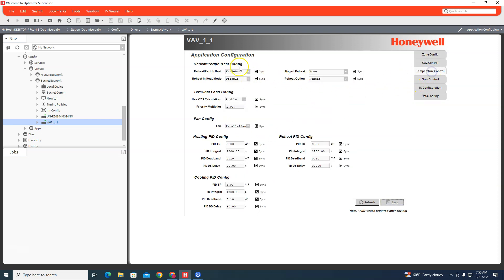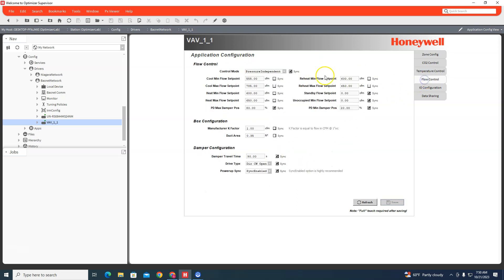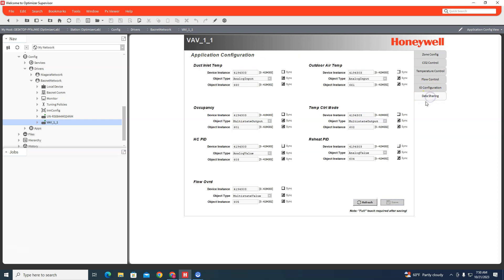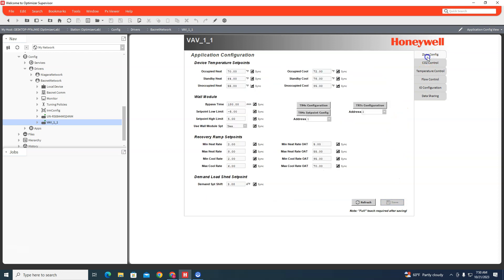And now you can go back in there and you can set all your set points, you can set CO2 if you're controlling that, how you're controlling temperature, flow control, if you want it pressure independent or pressure dependent. That's gonna show up what you're connected to it and data sharing, some of the stuff if you're going to share outdoor air temp to this controller or some other stuff to this controller.